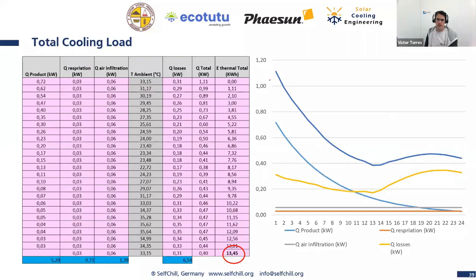Now let's look at the calculations. I did this for 1 day. These Excel files you will get for the next webinar, but just so you see how it looks when you don't take average temperature but the real cooling process and real ambient temperature. Here you see the cooling of the product over 24 hours. When we enter the product we have more, and then it's always less. You see this blue line, the Q product, going down, as we said.